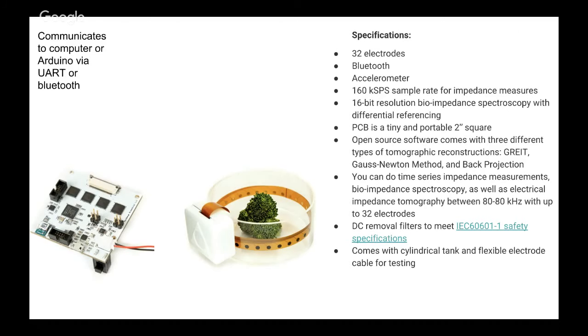So this is what it looks like. This is the Open EIT project. I call the device itself Spectra, because at different frequencies it gets a dielectric spectrum, and I think that's one of the most exciting parts about the information that it gets, which is this big dimensional data set, which would be ideal for machine learning. So basically it's got 32 electrodes, Bluetooth, accelerometer, pretty good sample rates, and 16-bit resolution of the analog to digital converter. You can do bioimpedance spectroscopy. It's really small, with open source software and a bunch of algorithms. The frequency range that it runs between is 80 hertz to 80 kilohertz. It's safe, and it comes with the cylindrical tank, which means that you can do testing in the phantom, which is the typical biomedical imaging test setup.